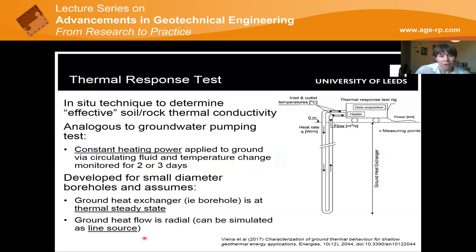Because piles are larger diameter than boreholes that this test was developed for, we have to run them for a longer time to get over the heat capacity of the concrete because of this steady state factor. This means we have to use a lower heating power to stop everything overheating. This means that we get a smaller rate of temperature change with time. And this means that we can get a fluctuation in the thermal conductivity we calculate at large times, as shown in this chart here, thermal conductivity against time in the test. We run a longer test, we get fluctuations at the end.